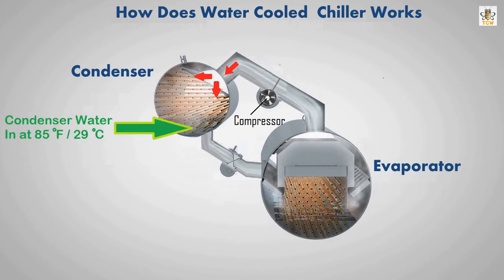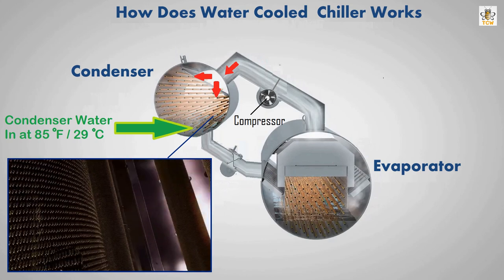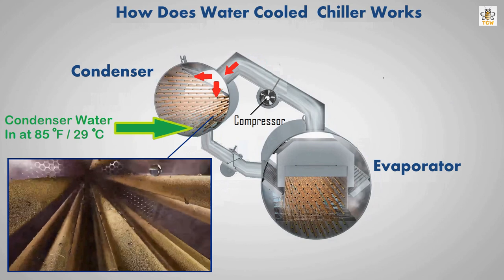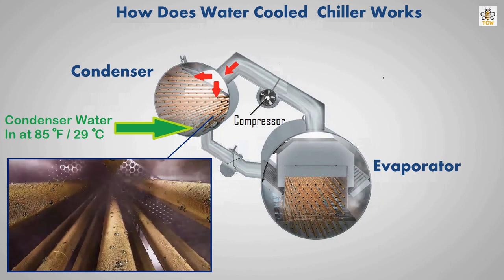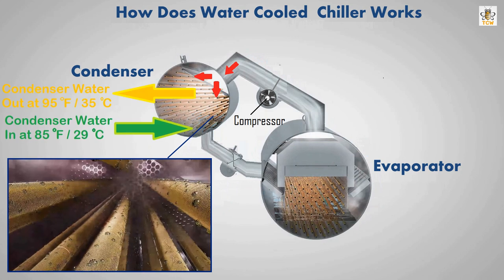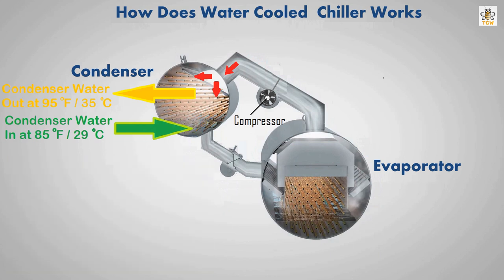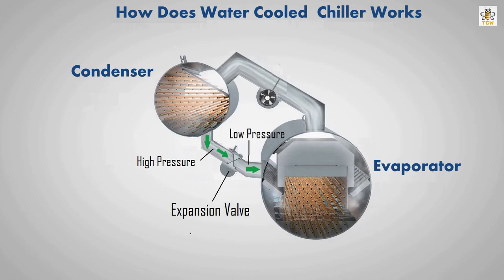The condenser water enters the condenser tank at 85 degrees Fahrenheit or 29 degrees Celsius. The refrigerant condenses as it flows on the cooler surface of the condenser tubing. Inside the tubing, condenser water absorbs heat from the refrigerant, and its temperature increases, flowing out at 95 degrees Fahrenheit or 35 degrees Celsius. The liquid refrigerant in the condenser tank flows back to the evaporator tank. An expansion valve maintains the pressure difference between the evaporator tank and condenser tank.